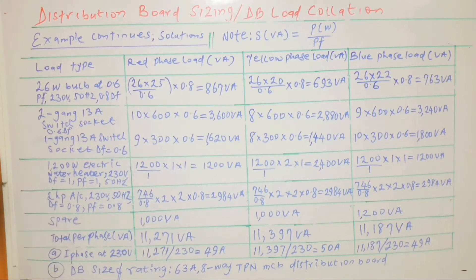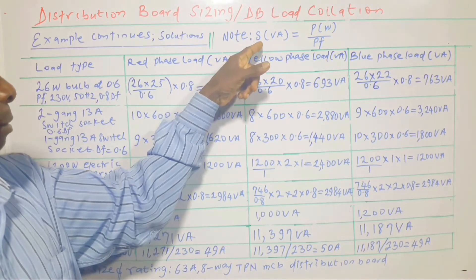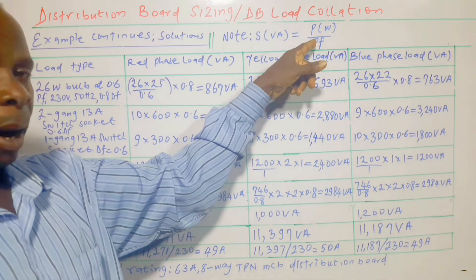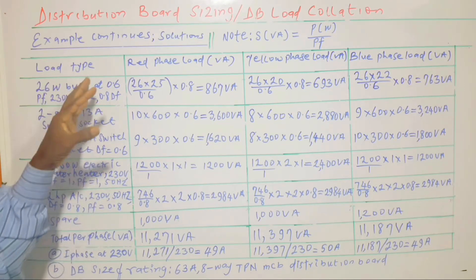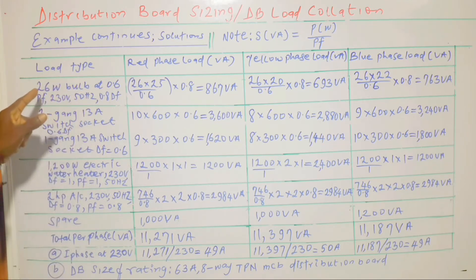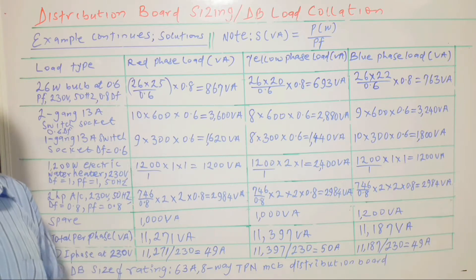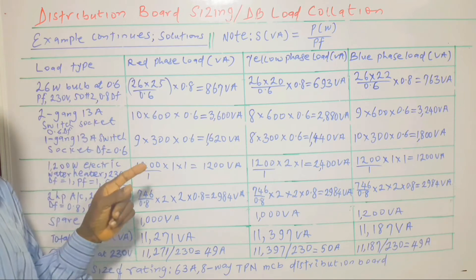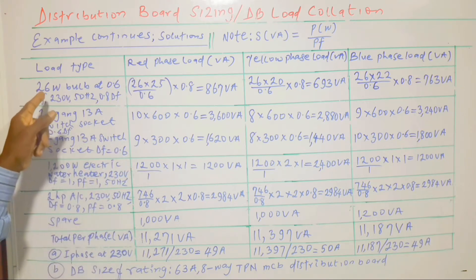The solution: note that the apparent power S in VA equals the active or real power in watts divided by the power factor. That is the major factor in what is being done here. For example, we have a 26-watt bulb at 0.6 power factor. The fact that all the bulbs will not be switched on at the same time means we introduce a diversity factor — a value less than 1 — which is multiplied by the total power requirement.